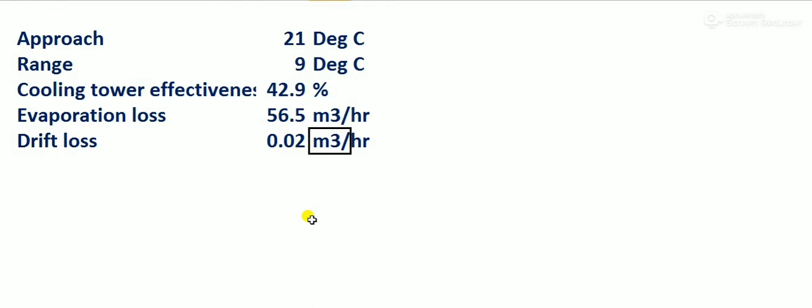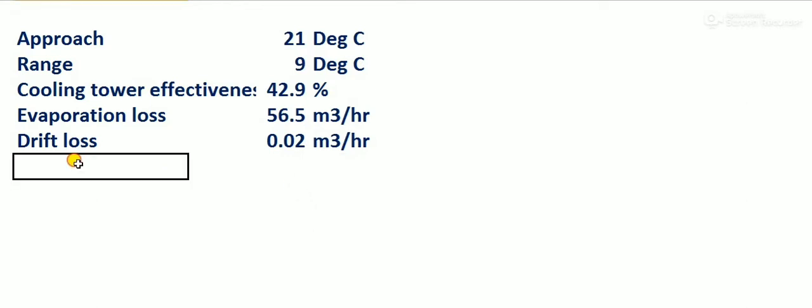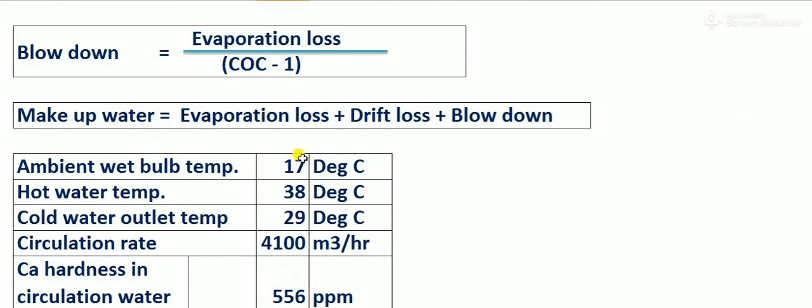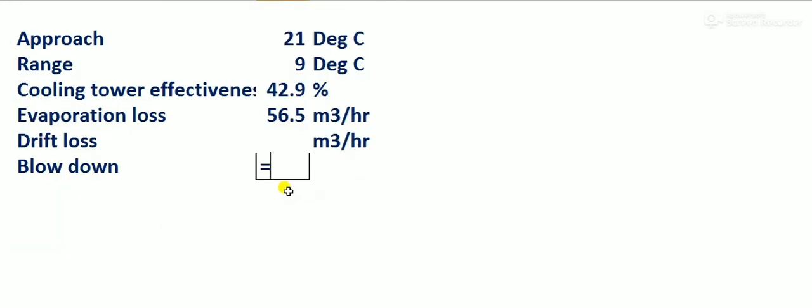So next we will go for blow down. Blow down is equal to evaporation loss divided by COC minus 1.